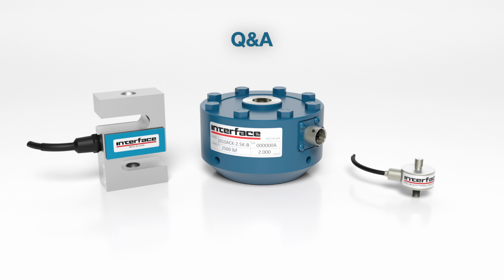How long can the cable be and still use an unamplified load cell? Okay, sorry, I didn't hear that initially. You can use whatever cable length you want with an unamplified load cell. However, you should probably use a sense or 6-wire configuration and ensure that your instrumentation supports that. There is a slight excitation voltage drop, and we have that information available online if you want to estimate it. But again, if you're using scaling data that assumes a full 10 volts gets to the sensor, and due to your 300 or 400 foot cable run it's now dropping to 9.6 volts, it's going to throw off your full scale data. So that's where a 6-wire or sense solution is the way to go.